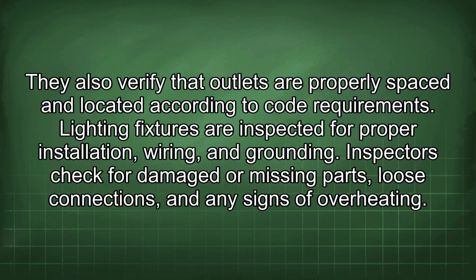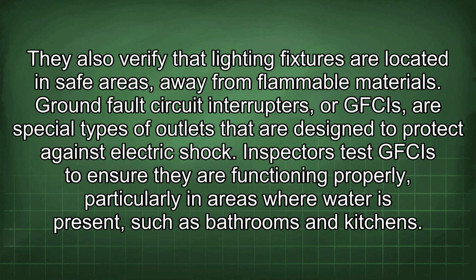Lighting fixtures are inspected for proper installation, wiring, and grounding. Inspectors check for damaged or missing parts, loose connections, and any signs of overheating. They also verify that lighting fixtures are located in safe areas, away from flammable materials. Ground fault circuit interrupters, or GFCIs, are special types of outlets that are designed to protect against electric shock.